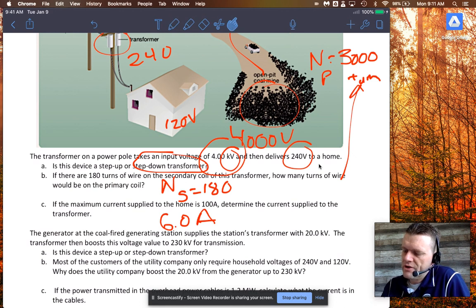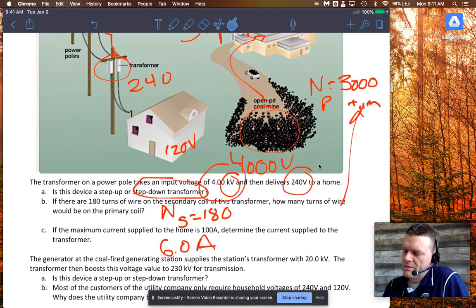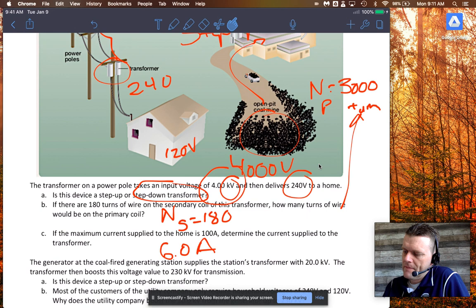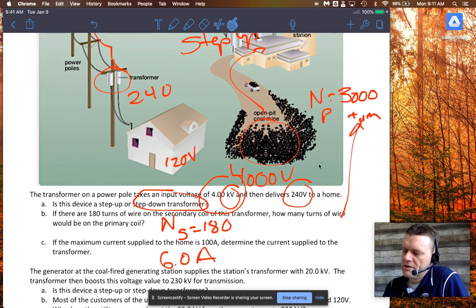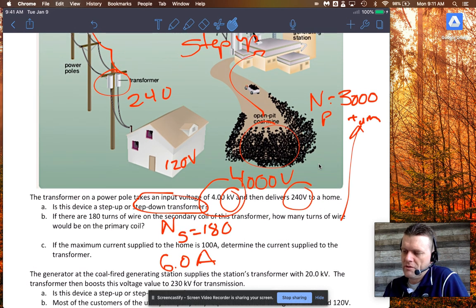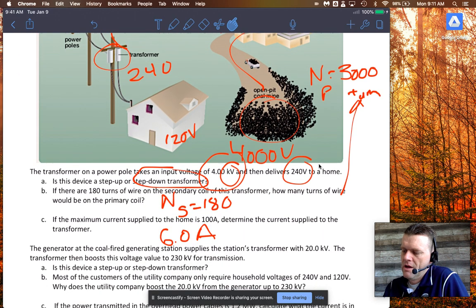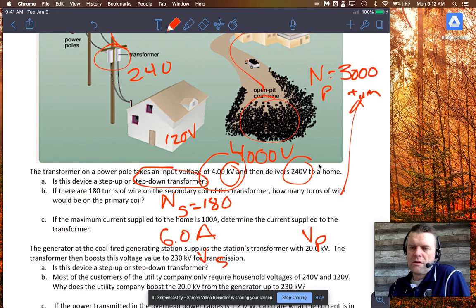At the coal-fired generating station, the station's transformer is provided with 20 kilovolts. The transformer then boosts this voltage to 230 kilovolts for transmission. So this is the primary voltage, and this is the secondary voltage, going from 20 to 230 kilovolts - same units, so that's fine. That's a step up; we're definitely increasing the voltage going from the power station to the transmission line.